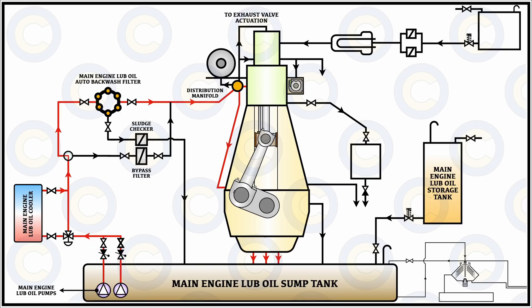In the two-stroke main propulsion engines, we have a completely different cylinder lubrication system where the source of oil, the pumps, and the lubricator are all completely different. The cylinder lube oil tank provides oil through filters and through a heater/cooler arrangement — simultaneously as per the requirement of your trade routes. For example, under cold routes you need a heater, and under normal routes you might need a cooler. It then goes to the cylinder lubricator, which helps with controlled pulse lubrication of the cylinder. In older generation engines, a manual lubrication system exists using capillary and manually-turned camshaft and gear arrangements.